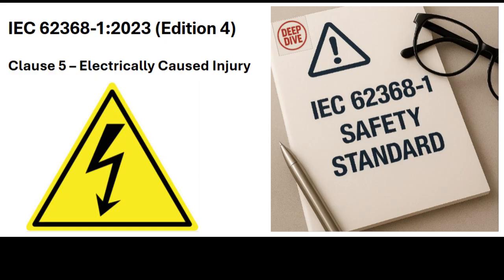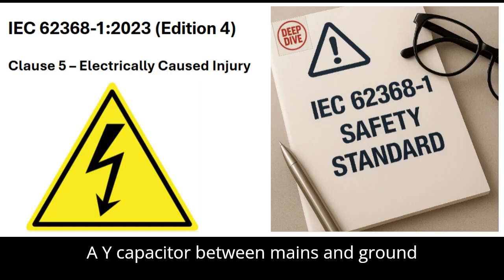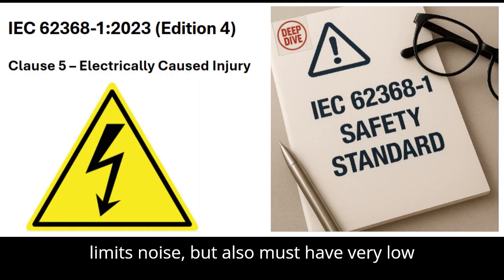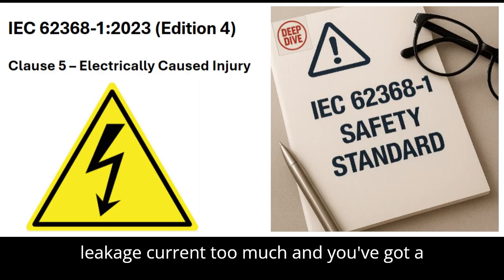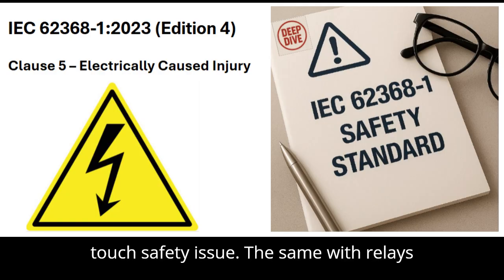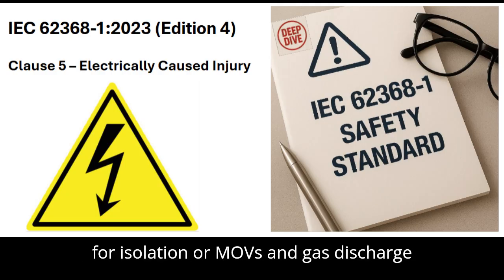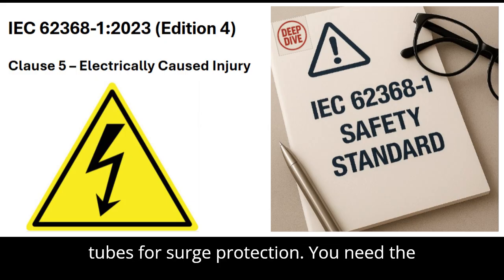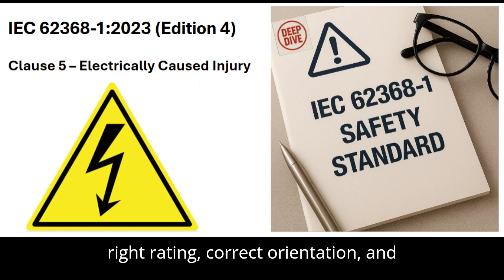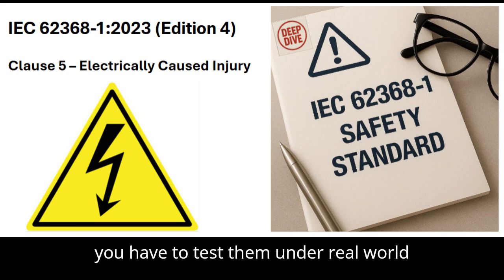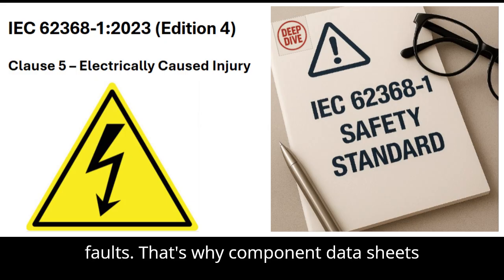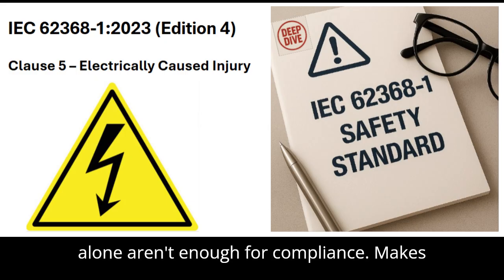As an example, a Y capacitor between mains and ground limits noise, but also must have very low leakage current. Too much, and you've got a touch safety issue. The same with relays for isolation or MOVs and gas discharge tubes for surge protection. You need the right rating, correct orientation, and you have to test them under real-world faults. That's why component datasheets alone aren't enough for compliance.